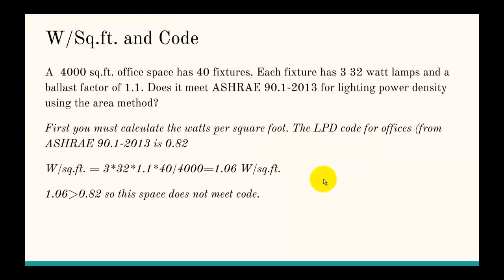Let's talk about another example. In this case we have a 4,000 square foot office space with 40 fixtures. Each fixture has three 32-watt lamps and a ballast factor of 1.1. Does it meet ASHRAE 90.1 code for lighting power density using the area method?